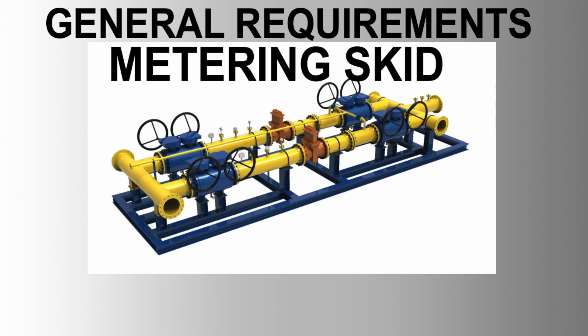Skid-mounted equipment considerations. Skid construction should allow for easy operation and maintenance of all equipment, with graded floor-type walkways, handrails, and ladders as required. Skid-mounted systems should include all necessary pipework, instrumentation, and cabling to minimize site work. Structural steelwork should be designed according to relevant standards and provide adequate support and access for all components. These detailed requirements ensure the reliability, accuracy, and safety of metering systems in various industrial applications.